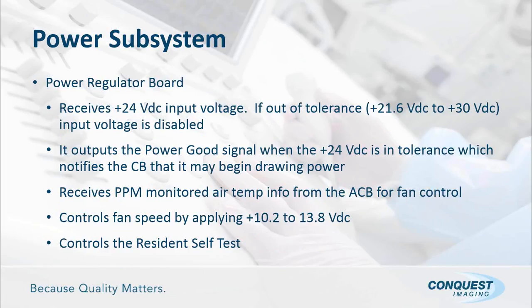You have a power regulator board, and this system DC voltage is 24 volts, and it has circuitry to monitor the tolerance, 21.6 to 30 volts DC, and if it exceeds those limits, then it simply powers itself down, and it won't allow you to power up. When the power good signal, the 24 volts, is in tolerance, it notifies a channel board that, hey, by the way, you're good to go. You're good to draw any power at that point.